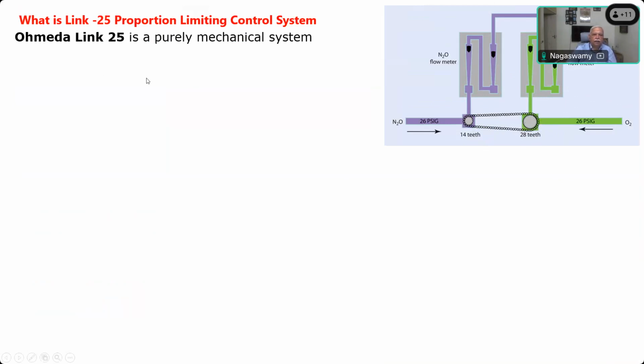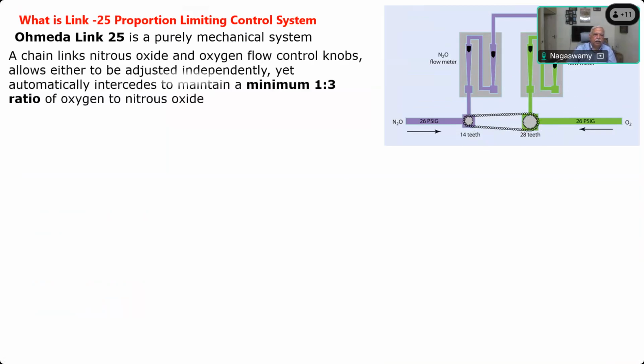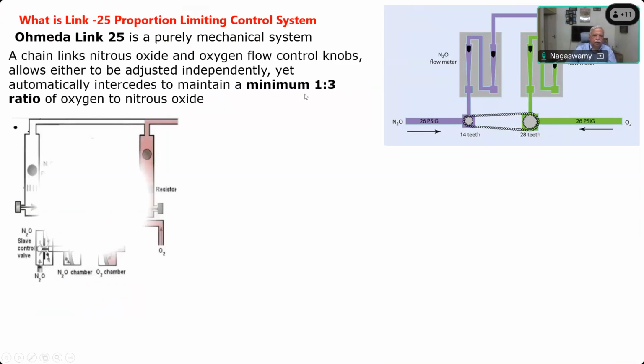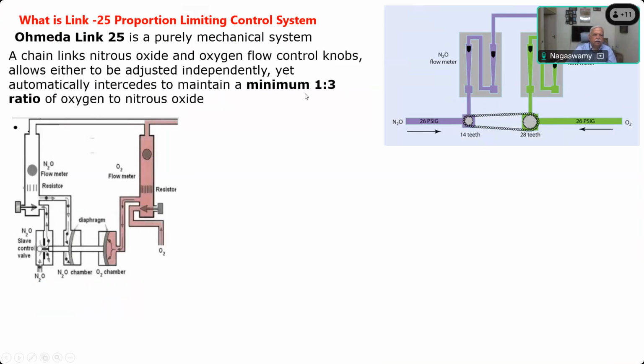It is a purely mechanical system. A chain links the nitrous oxide and oxygen flow control knobs and allows either to be adjusted independently, yet automatically intercedes to maintain a minimum 1:3 ratio of oxygen to nitrous oxide. So always you will get 25% out of the 100% that you use. You can use 75% nitrous oxide, but still get 25% oxygen. What is shown here, and how does this work?